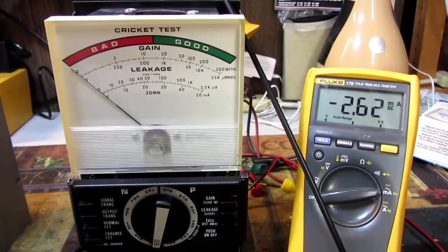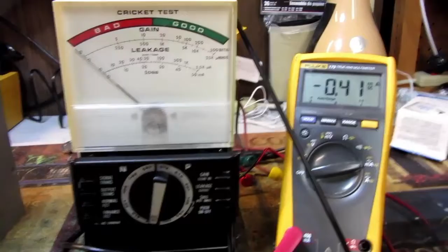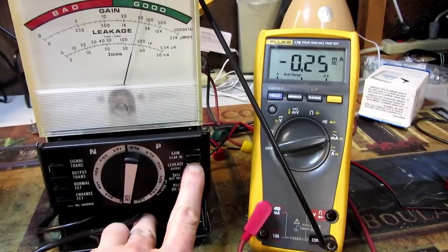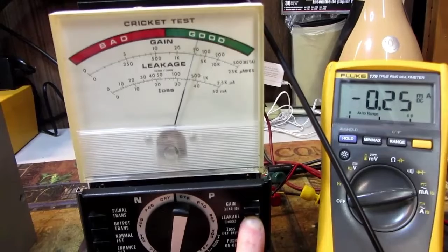That is R38, which is the one that you adjust first. Next, we will adjust R39 for 250 microamps. So you'll reset the resistance until when you press the leakage button, you have 250 microamps. Now I've readjusted the resistance for 250 microamps when I press the leakage button here. As you'll see, it's reading 0.25 mA. And you want to have the scale right between the 200 and 300 on the microamp range. Okay, the 250 microamp range is right here.